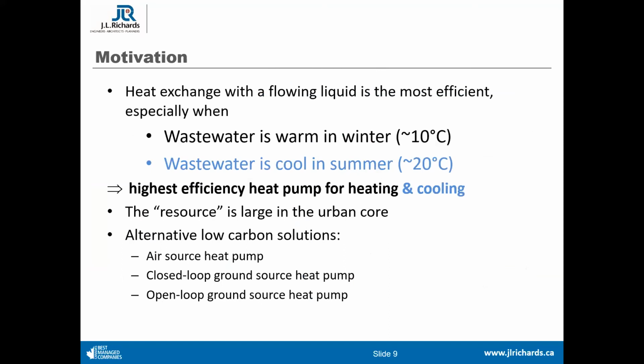The motivation behind this is that heat exchange with a flowing liquid is one of the most efficient ways to exchange heat. We're doing it with wastewater, which is warm in winter, around 10 degrees, and cool in summer, around 20 degrees - much more moderate temperatures than, for example, an air source heat pump, which draws heat from below-zero air and pumps it into 30-plus degree air in summertime.